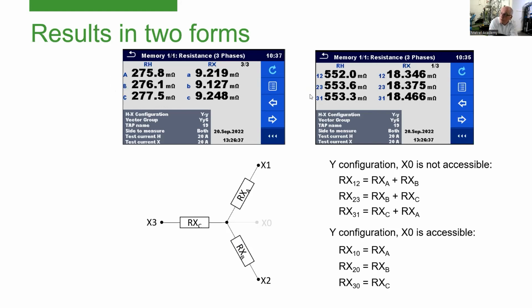One screen is the winding resistance between terminals. This is the typical output of other instruments from competitors. The second screen gives you the information about the winding resistance of the individual windings, winding A, winding B, winding C. This result gives you a much better overview of whether everything is okay. There is no big difference between one form and the other. But if there is something wrong in the windings, if there are some contacts in between individual windings, it is much more visible in this form where the problem is.